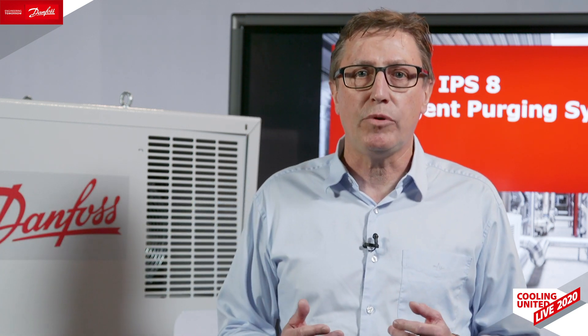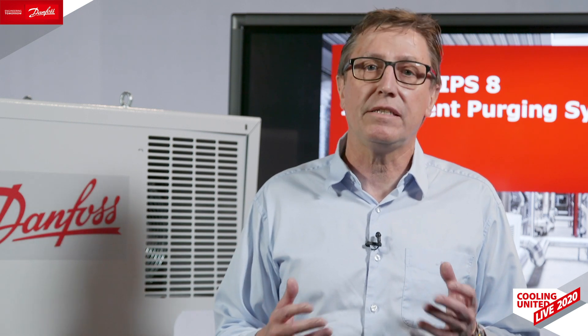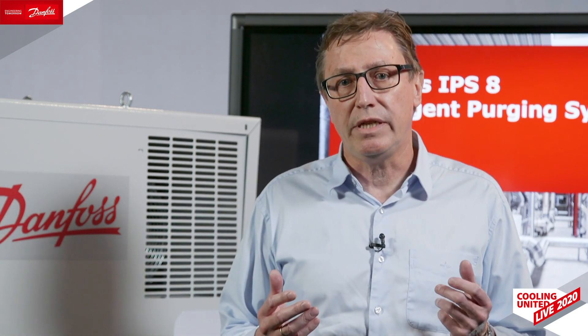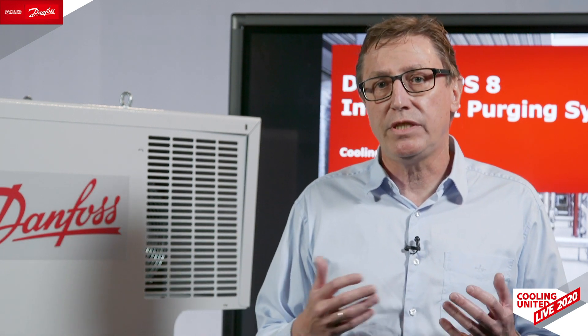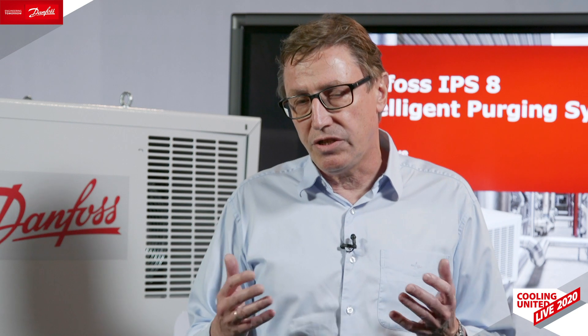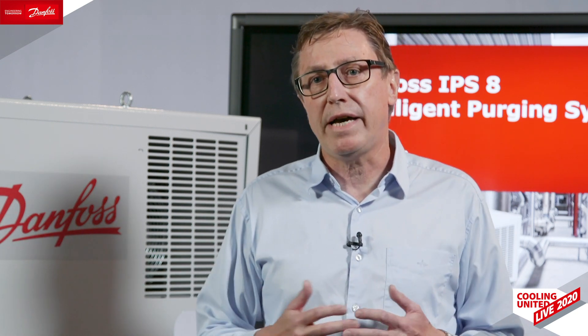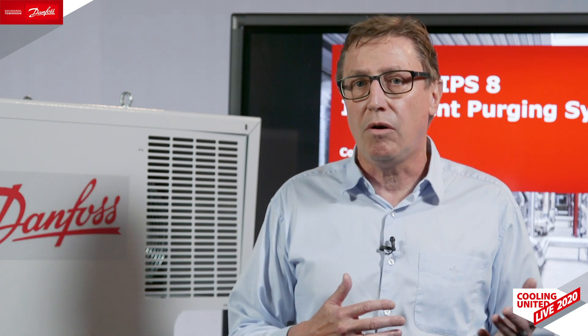Why is it a good idea to have an air purger? Air is the most common non-condensable gas impacting industrial refrigeration systems. We can face this issue during operation or service. During operation, if you are vacuuming the system at about minus 33°C in ammonia, you will lead to a passage of air as a non-condensable gas. It could also occur during service if you need to charge refrigerant — ammonia or oil — that could lead to such an issue.